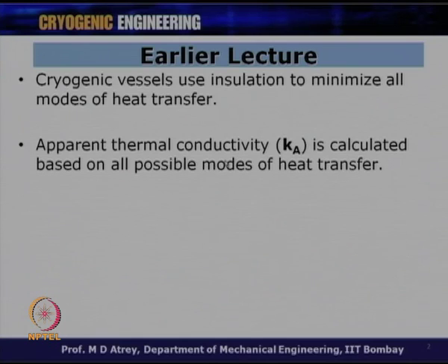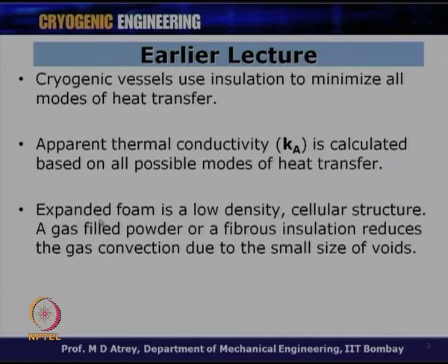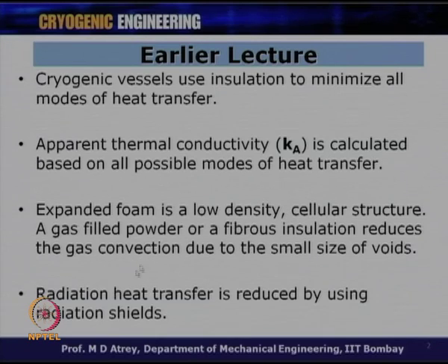The apparent thermal conductivity Ka is calculated based on all possible modes of heat transfer — it takes into account conduction, convection, radiation, etc. We found that expanded foam is a low density cellular structure. A gas filled powder or fibrous insulation reduces gas convection due to the small size of voids. Radiation heat transfer is reduced by using radiation shields, and putting many shields reduces radiation heat transfer.